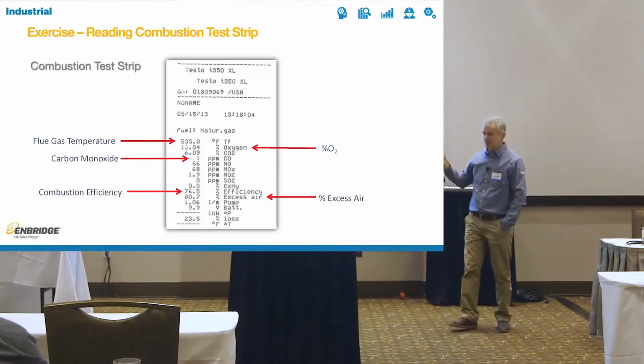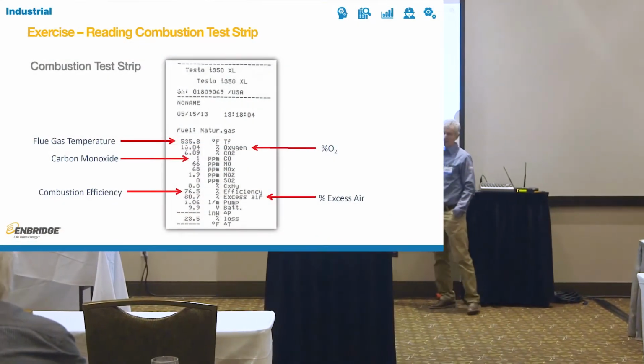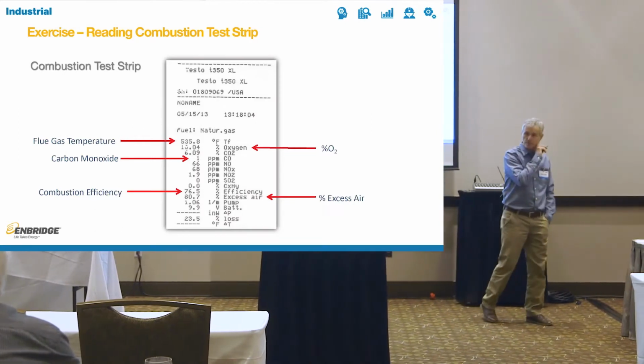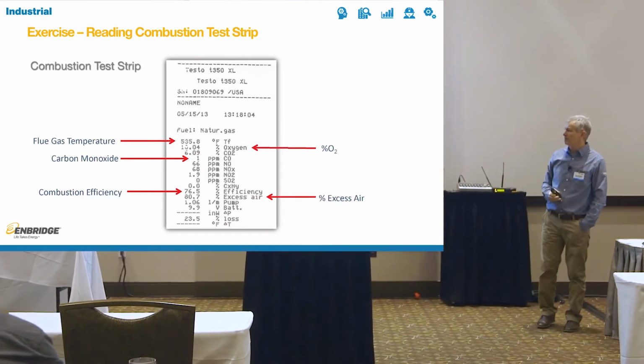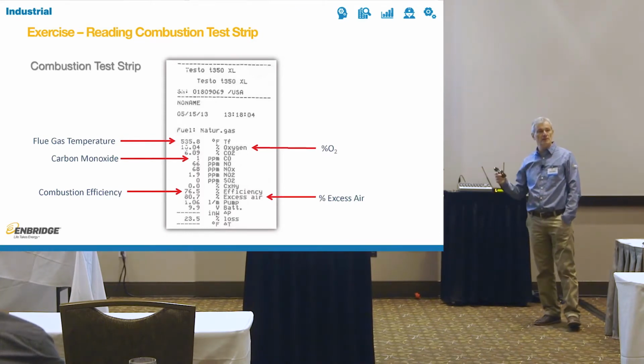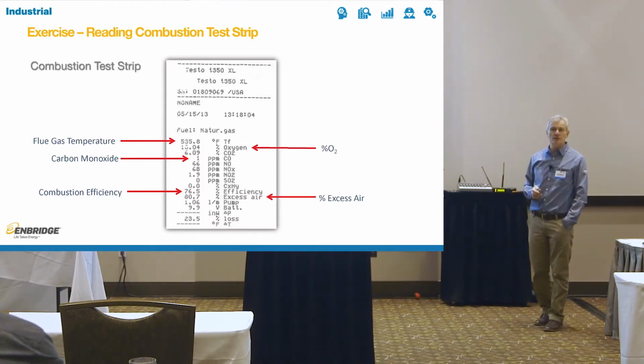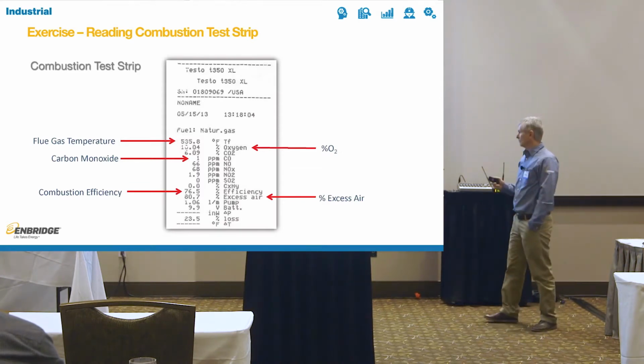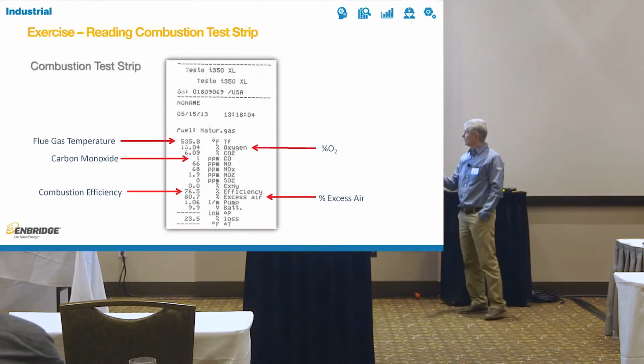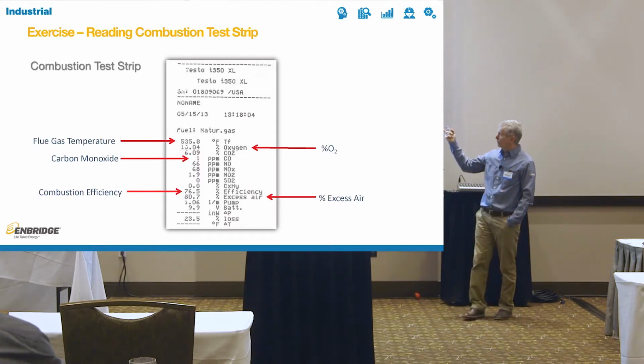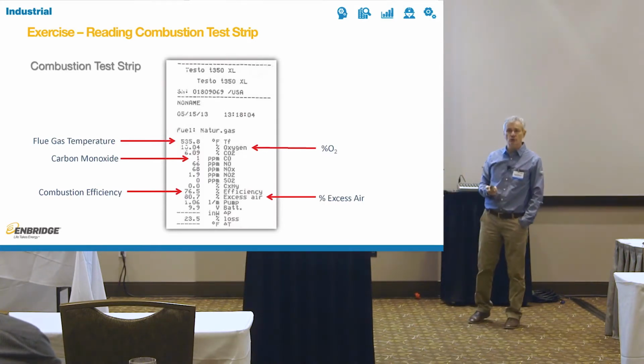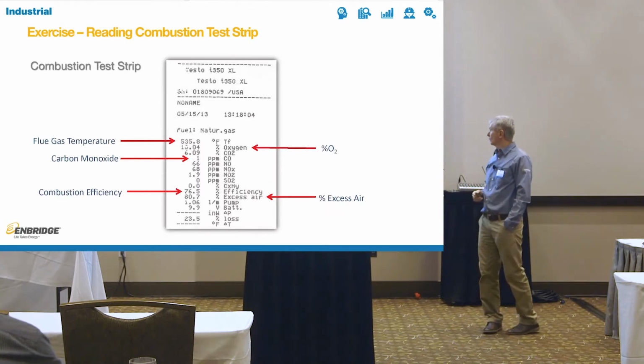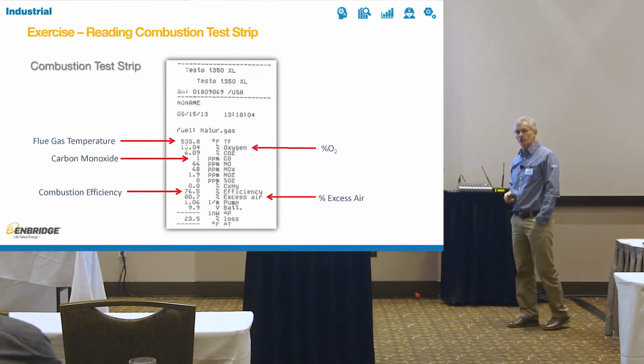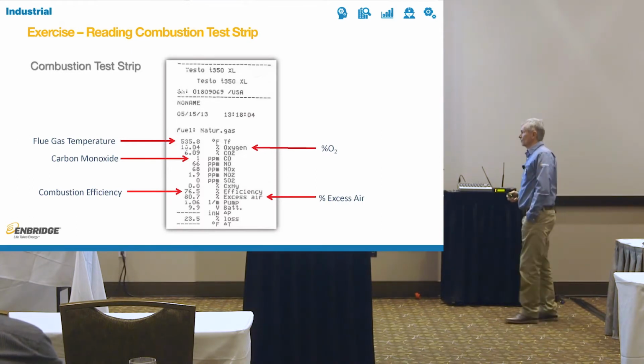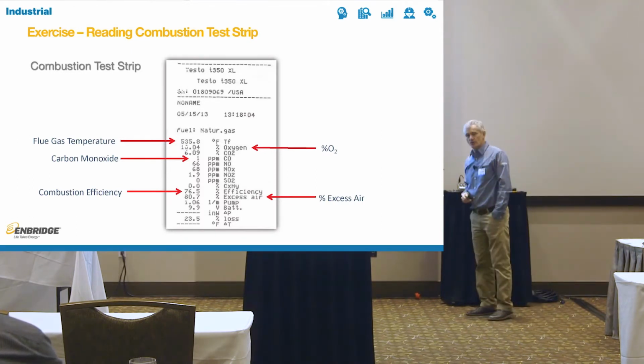So thank you, Chris, for that. That was good. Again, a reminder for everybody, this piece here is the most important piece of paper you can get if you ever get somebody to do your combustion testing. Because people usually come do their combustion testing once a year, and they can never produce their test strips. The key points to keep in mind: flue gas temperature, so you know how much heat you're putting out the stack, how much oxygen is in there, how much carbon monoxide, and combustion efficiency.